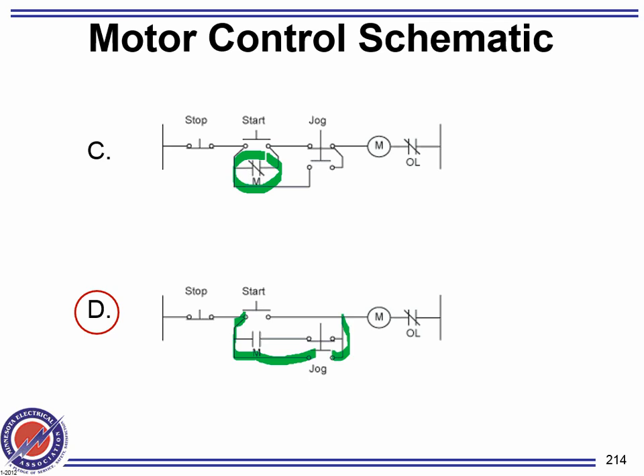No? Is that the bypass? Yes or no? Yeah, that's a bypass. Now, the normal stop would be right next to it, of course. So that's where you go normally. Current comes in here, goes through. Now, under normal condition, then this will close and it goes through here. That's the normal operation.